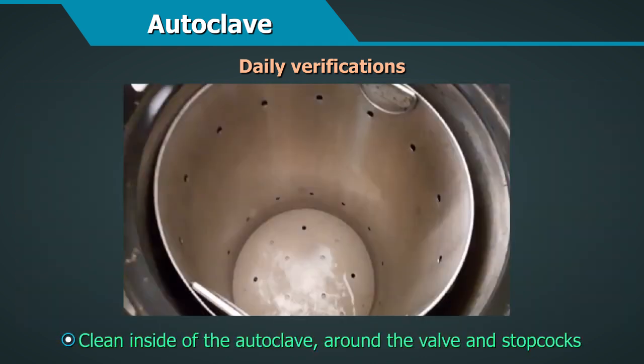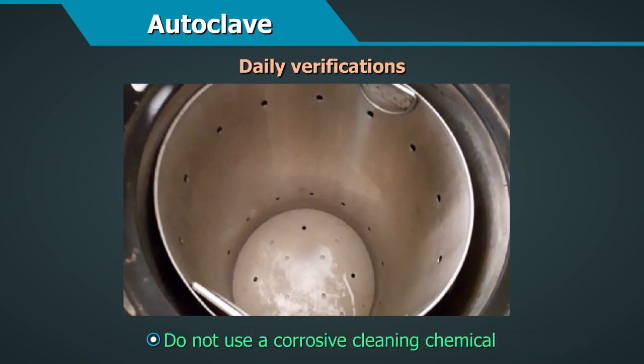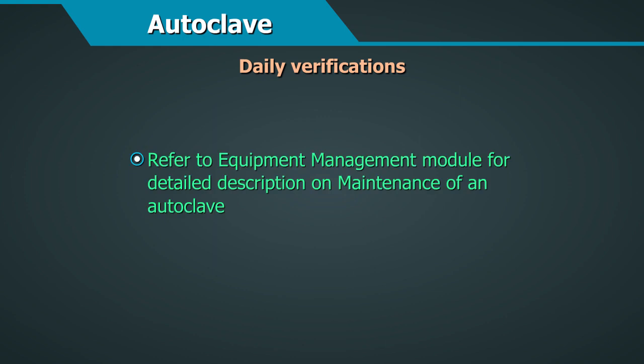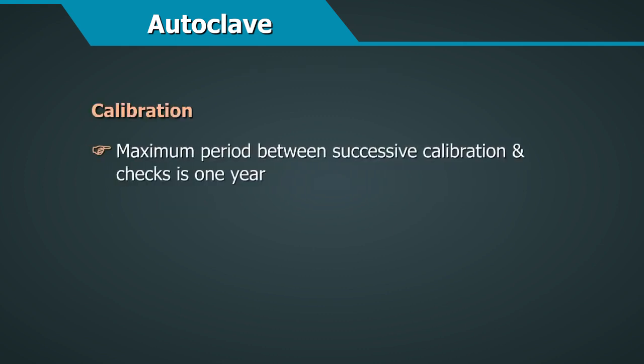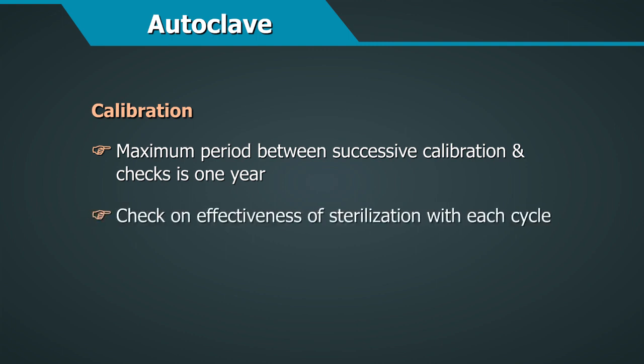Clean the inside of autoclave after use and also around the valve and stopcocks. Make sure that the vent is not blocked. Do not use a corrosive cleaning chemical. Refer to Equipment Maintenance Module for a detailed description on maintenance of an autoclave. Calibration. Maximum period between successive calibration and checks should be 1 year. Check on effectiveness of sterilization with each cycle.